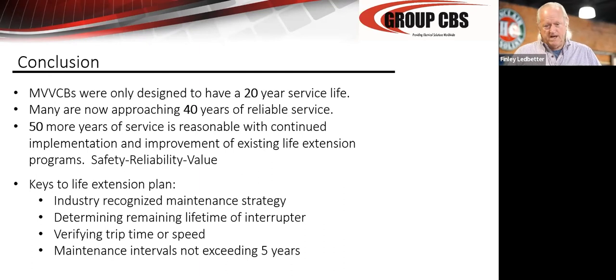You can't do a velocity and travel test in a couple of minutes. Maybe you would do that on critical circuits occasionally, but the basic parting test tells you everything you need to know from a maintenance standpoint. And I would do it every time you maintain the breaker, every time you look at the breaker, which I would say is less than every 5 years. Basically, when things start to go sideways from lubrication, from a contaminant standpoint, or a spring or anything, it'll show up in that timing test.